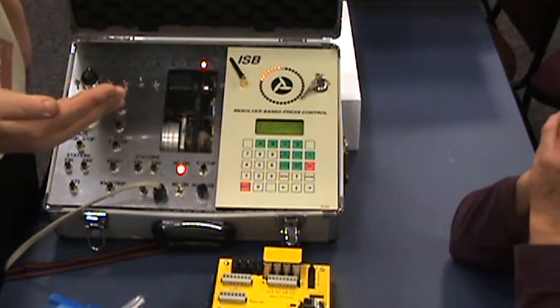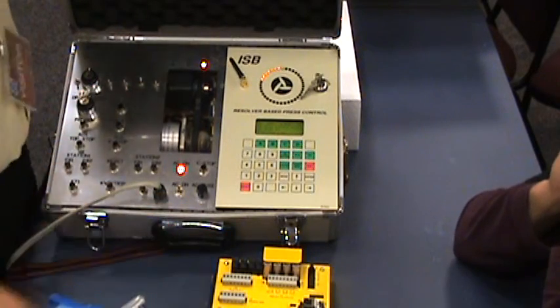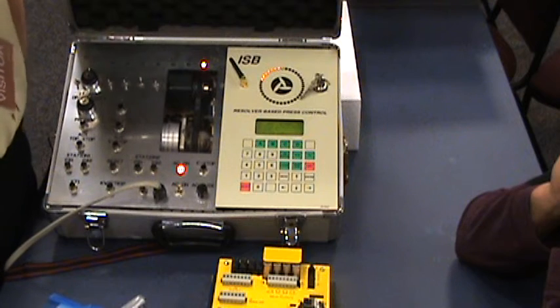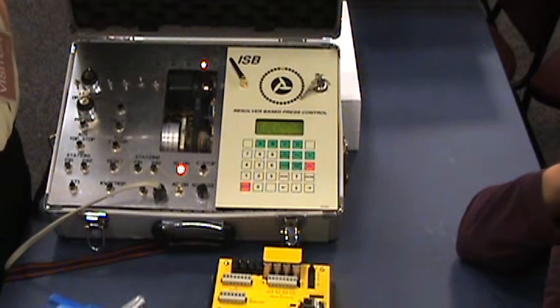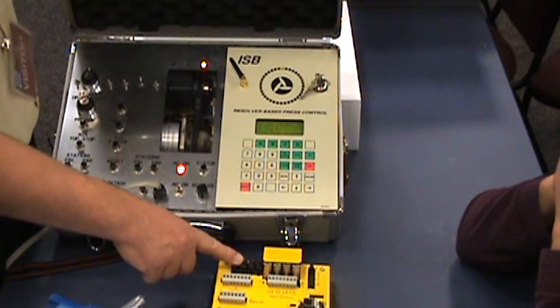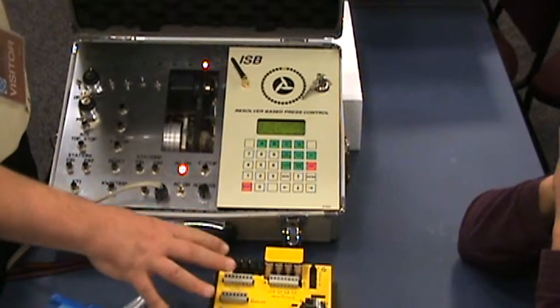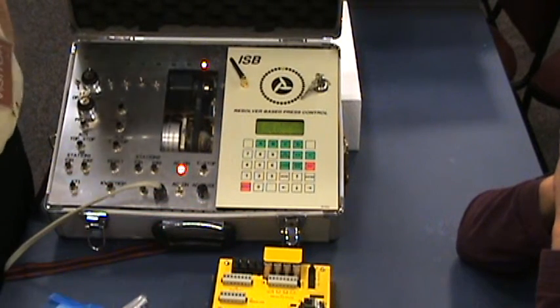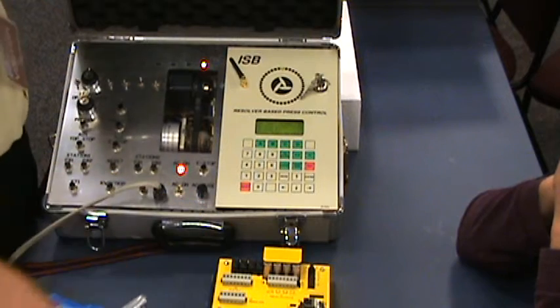So, if it's an AC solenoid, you need an AC solid state relay. If it's a DC device, it's not going to work with an AC solid state relay. You have to then put the appropriate relay in the socket. There's two types, AC or DC solid state. A mechanical relay can turn on and off anything. It's a switch. It's a dry switch. So, we supply them with the dry switches, but we'll give you any combination when you order the unit that you want. And you can always buy extra replacements and plug them into those sockets.